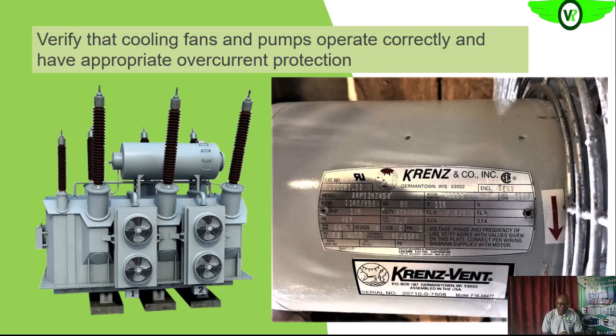So we want to look at the cooling fans to be sure that they are operating appropriately. The direction of rotation is the right direction that will force air to the direction we want the air to be forced. If it is to remove air, that is to create vacuum within the transformer fins, you should be able to extract air from the transformer or blow air to the transformer. We want to be sure that the blade is actually in the right direction.